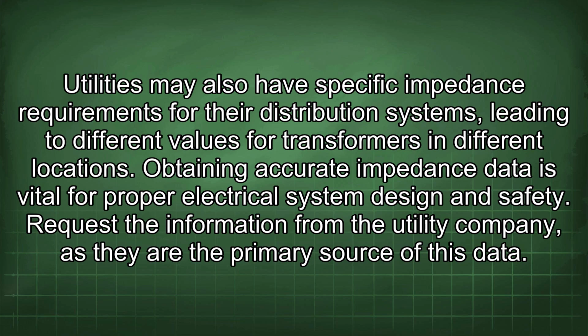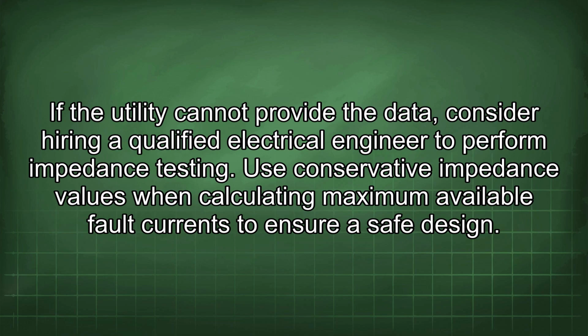Obtaining accurate impedance data is vital for proper electrical system design and safety. Request the information from the utility company, as they are the primary source of this data. If the utility cannot provide the data, consider hiring a qualified electrical engineer to perform impedance testing. Use conservative impedance values when calculating maximum available fault currents to ensure safe design.